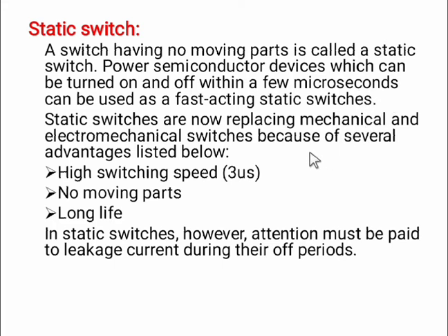Now static switches are replacing mechanical and electromechanical switches because of the following advantages. It has high switching speed, 3 microseconds. That means we can turn on the switch within 3 microseconds and turn off the switch within 3 microseconds after applying the control signal or gate signal. There are no moving parts, so it has no maintenance and a long life. The only disadvantage of the static switch is that while the switch is in the off condition, some amount of leakage current will flow.